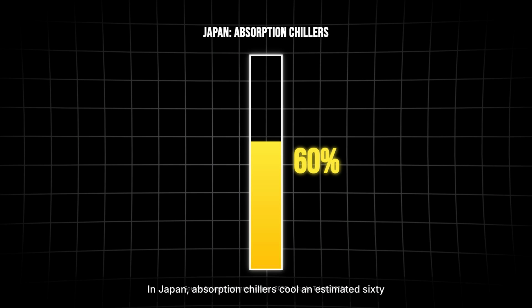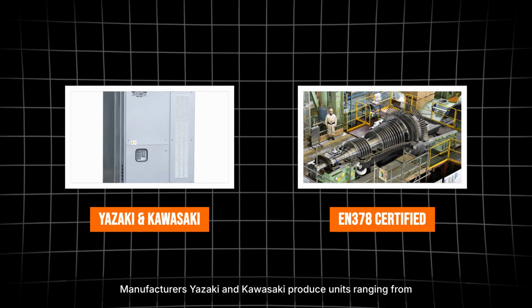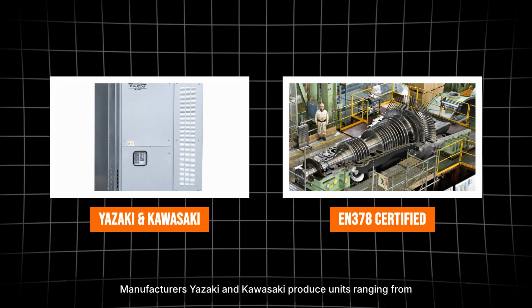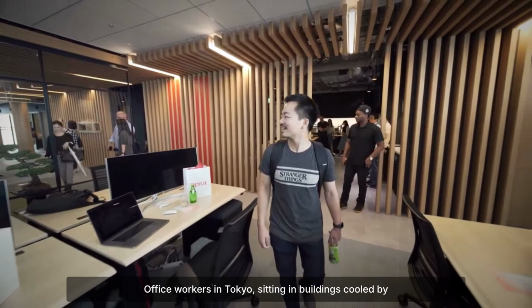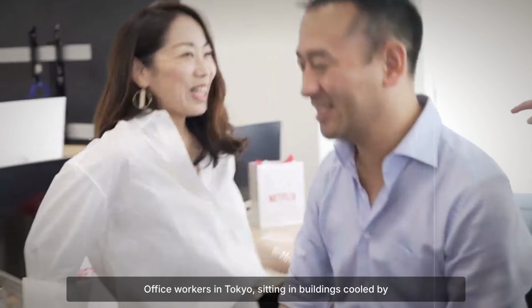In Japan, absorption chillers cool an estimated 60% of all commercial buildings. Manufacturers Yazaki and Kawasaki produce units ranging from residential 10-kilowatt systems to industrial megawatt installations. Office workers in Tokyo sitting in buildings cooled by ammonia.